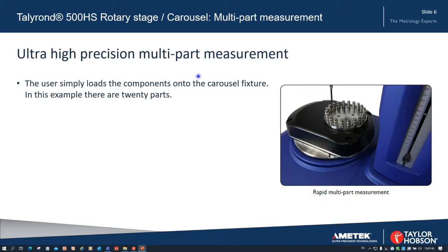The user simply loads these components onto the carousel fixture, and in this example here there are 20 parts fitted. What happens is the carousel rotates to bring the selected part over the instrument spindle axis, and if you look on the right you can see one of the parts is over the center of the spindle axis, and that's the one that's going to be measured.